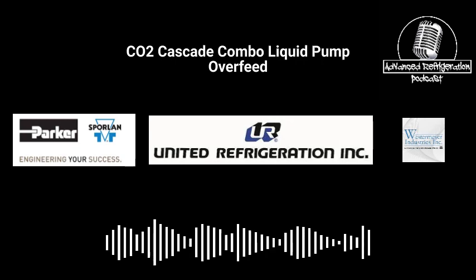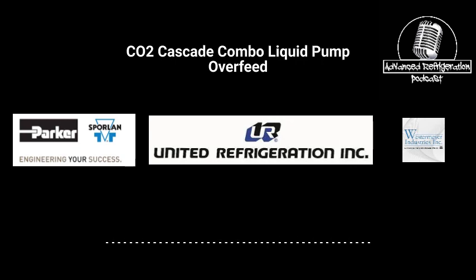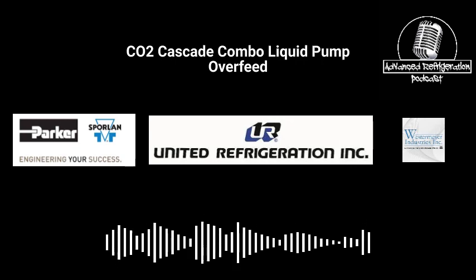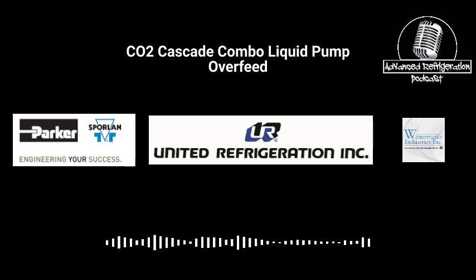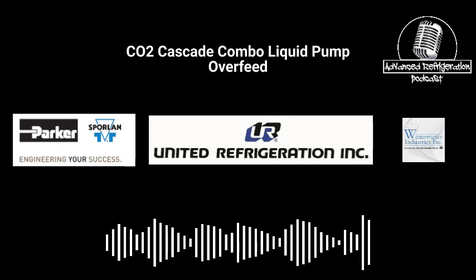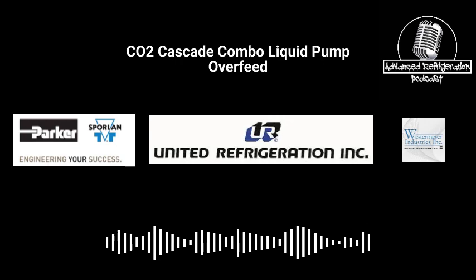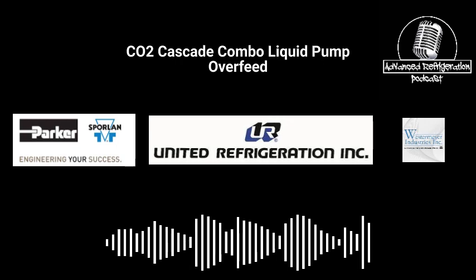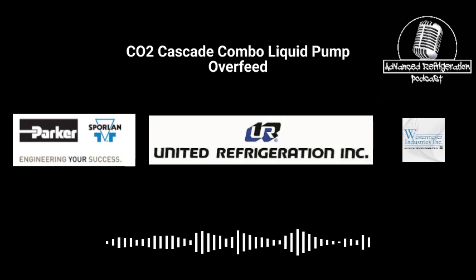But when it does turn back on, there are, I think, 6 different timing relays that are set for certain times. If you look within the schematic, it'll show you this one's supposed to be set for this time, this one's supposed to be set for this time, and this one for this time. So you don't bring on all that load all at once, especially after a potential failure. Probably all crews have those time delays, and every time there's a power outage, probably half of them are out.